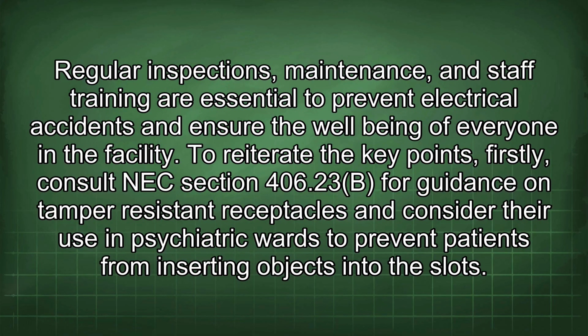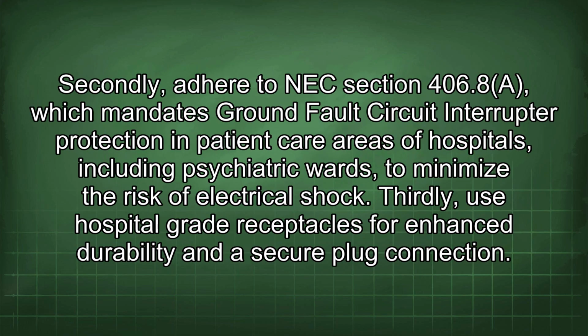406.23B for guidance on tamper-resistant receptacles and consider their use in psychiatric wards to prevent patients from inserting objects into the slots. Secondly, adhere to NEC Section 406.8A, which mandates ground fault circuit interrupter protection in patient care areas of hospitals, including psychiatric wards, to minimize the risk of electrical shock. Thirdly, use hospital-grade receptacles for enhanced durability and a secure plug connection.